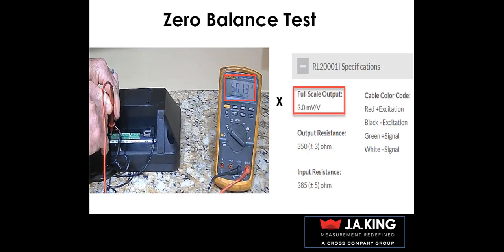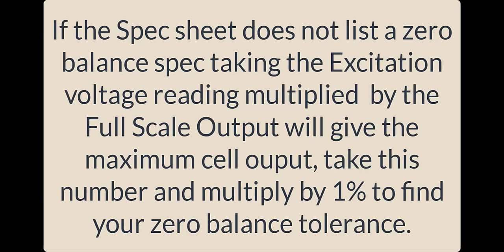The full-scale output is attained by taking the excitation voltage and multiplying by the full-scale output on the spec sheet. So in this example, we got 5.013 multiplied by the 3 millivolts would be a 15.039 millivolt at full-scale capacity. If the spec sheet does not list a zero balance spec, taking the excitation voltage reading multiplied by the full-scale output will give the maximum cell output. Take this number and multiply by 1% to find your zero balance tolerance.